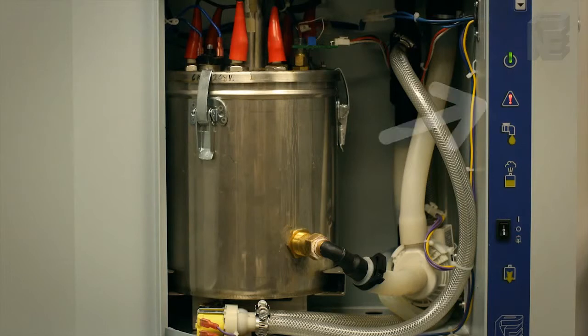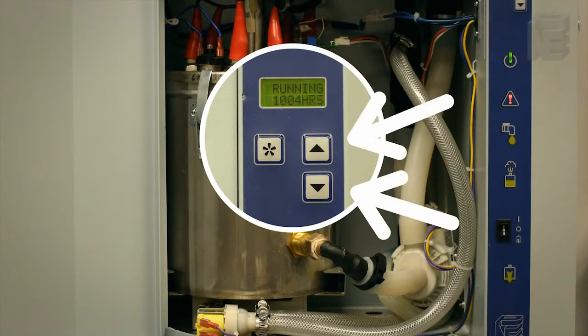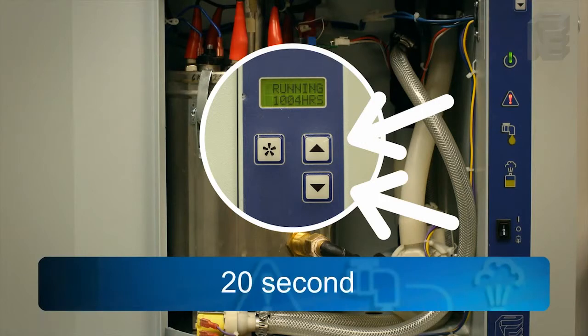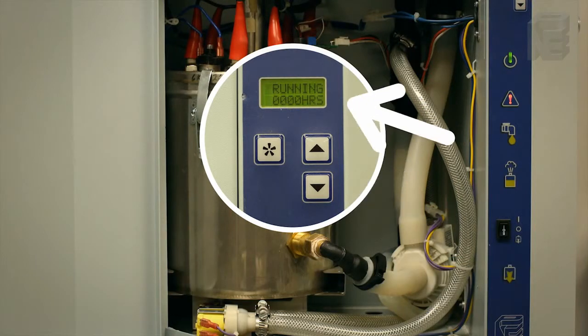In order to erase the red LED check light after servicing is complete, go to hours run in the menu and hold down the up and down arrows simultaneously for 20 seconds or until the hours are zeroed.